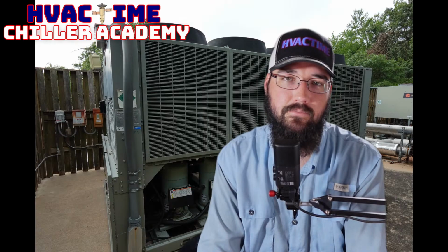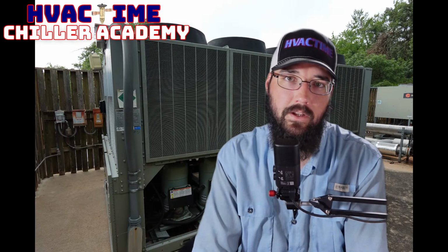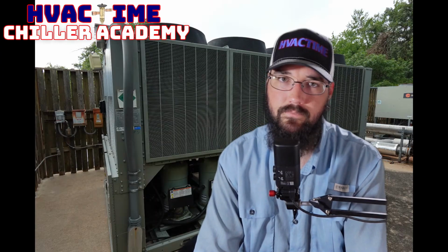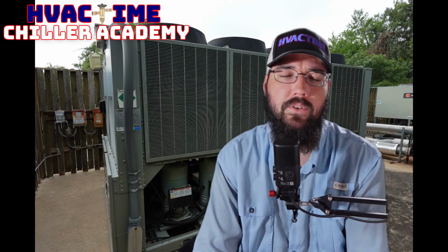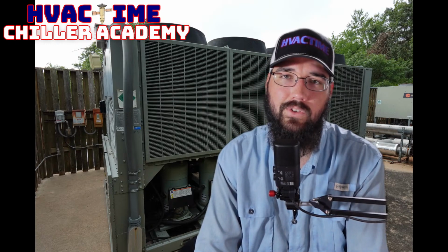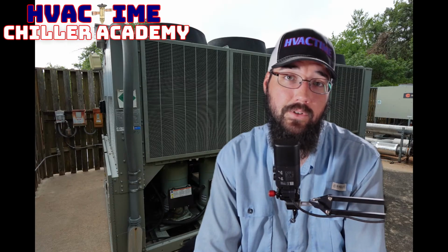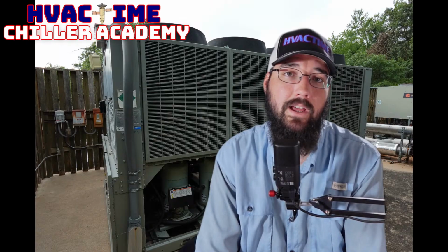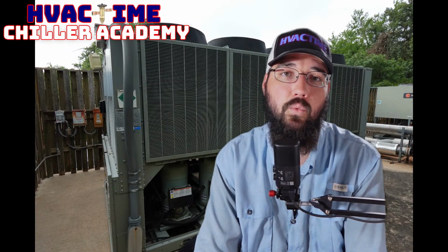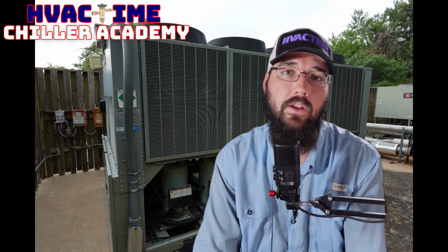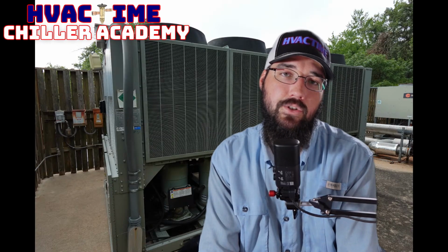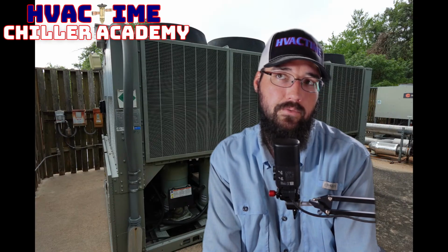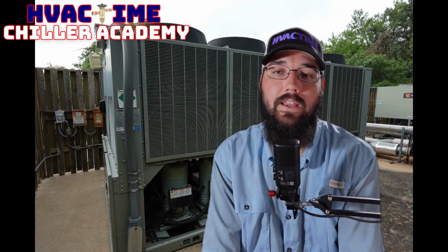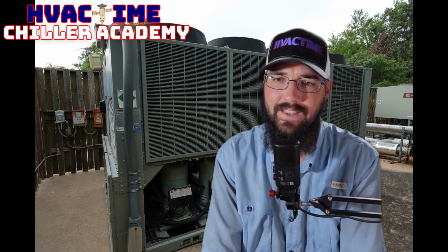That electric usage is going to be substantially higher, because every time they got to turn both of those compressors on, the chiller turning on at that point, it's going to be seeing water in the 50s, so it's going to want to stage up to a high load thinking it has a hot pull down to do. In reality, it's a warm loop with a light load, and they're doing a weird control sequence trying to base it off of load. It's fine if they want to do that early in the mornings when they're still unoccupied, and then not let the chillers turn on until the load reaches past a certain, call it, staging point. But they can't leave it like that long term.